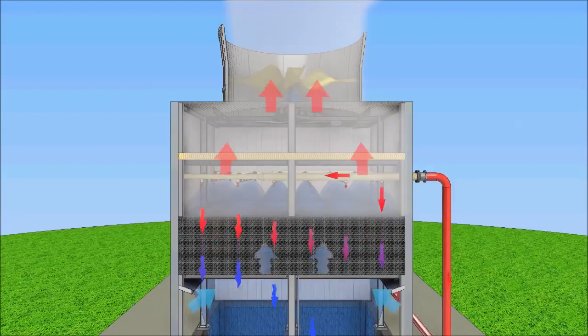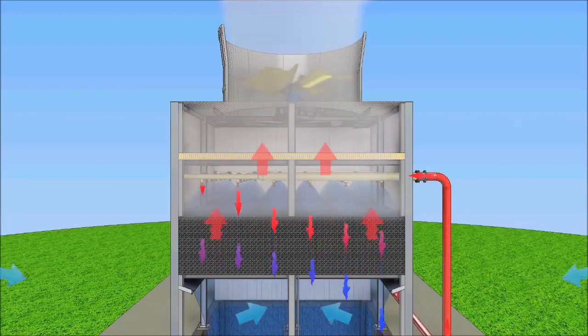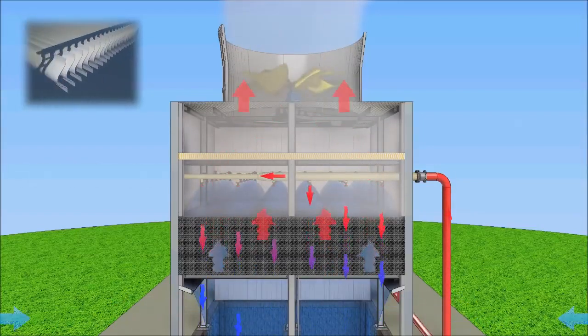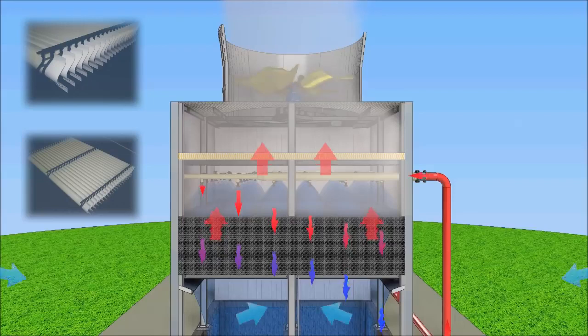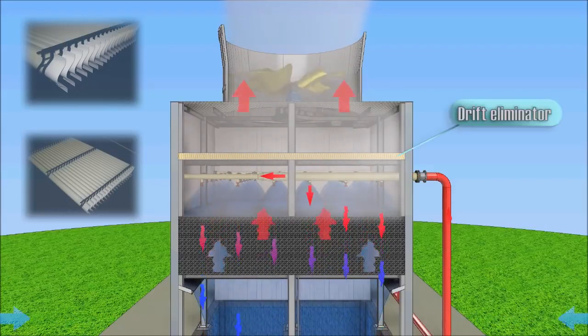Operating a cooling tower emits air saturated with water vapor and containing water droplets with sizes of 100 to 500 microns. To prevent entrainment of water droplets, above the water distribution system is installed a drift eliminator.